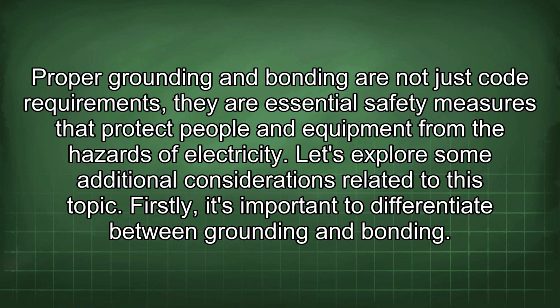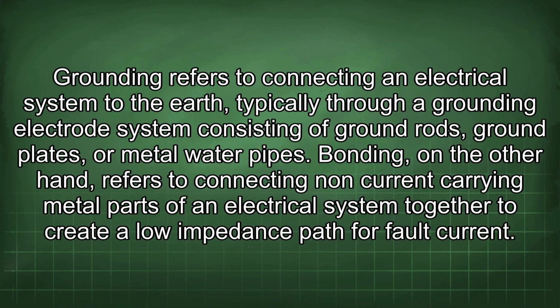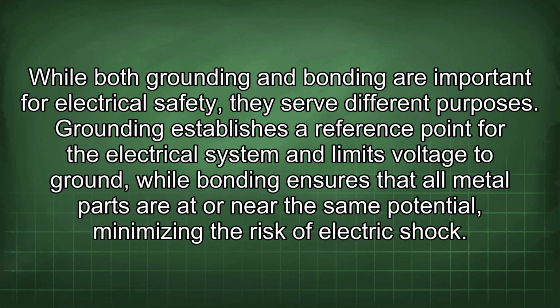Firstly, it's important to differentiate between grounding and bonding. Grounding refers to connecting an electrical system to the earth, typically through a grounding electrode system consisting of ground rods, ground plates, or metal water pipes. Bonding, on the other hand, refers to connecting non-current carrying metal parts of an electrical system together to create a low impedance path for fault current. While both grounding and bonding are important for electrical safety, they serve different purposes.